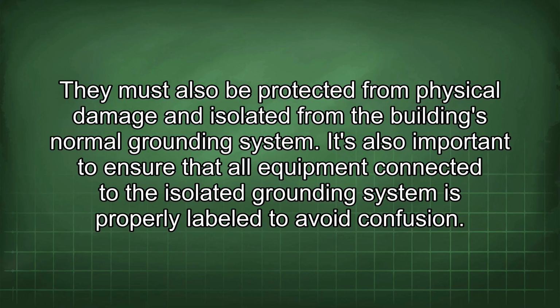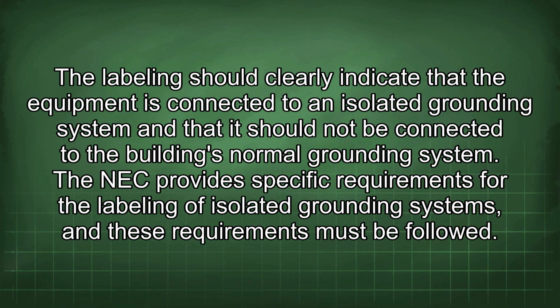It's also important to ensure that all equipment connected to the isolated grounding system is properly labeled to avoid confusion. The labeling should clearly indicate that the equipment is connected to an isolated grounding system and that it should not be connected to the building's normal grounding system. The NEC provides specific requirements for the labeling of isolated grounding systems, and these requirements must be followed.